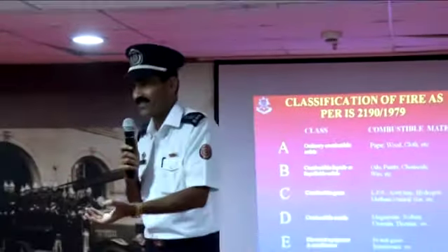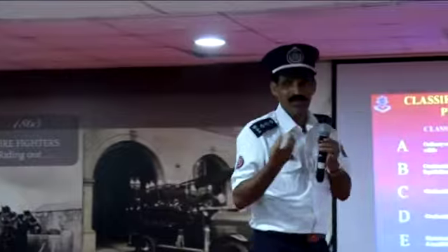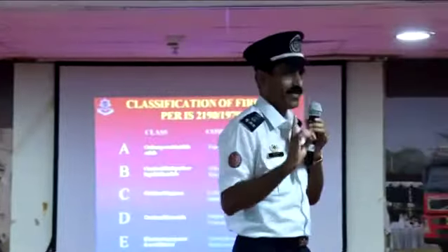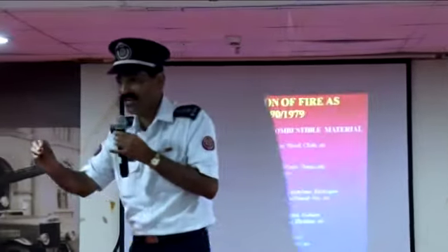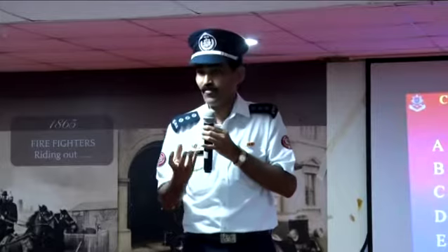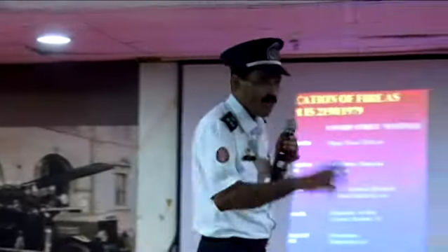Excellent. Because what happens now? Water is denser than oil. Oil is lighter, water is heavier. When you pour water on that fire, being heavier, it goes to the bottom. And water has another bad property. The expansion ratio of water into steam is 1700 times. If you pour 1 liter, you will get 1700 liters of steam. So it requires that much volume. To accommodate that volume, the lighter oil will be thrown out.